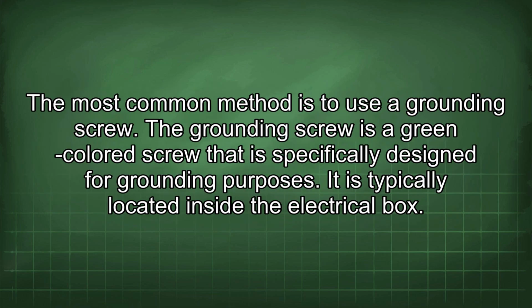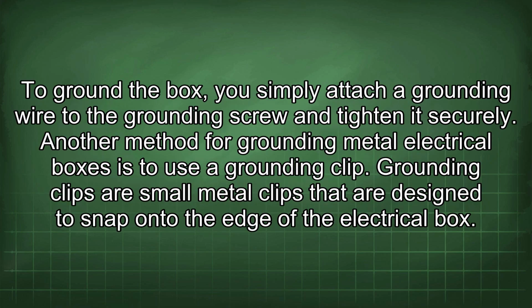The most common method is to use a grounding screw. The grounding screw is a green-colored screw that is specifically designed for grounding purposes. It is typically located inside the electrical box. To ground the box, you simply attach a grounding wire to the grounding screw and tighten it securely.